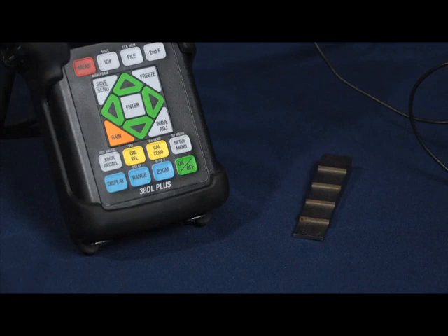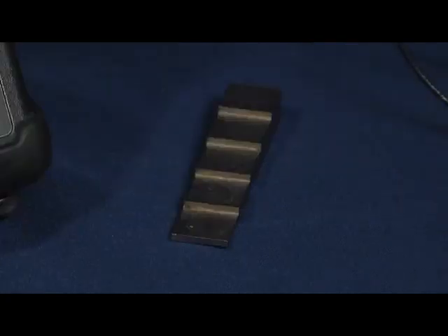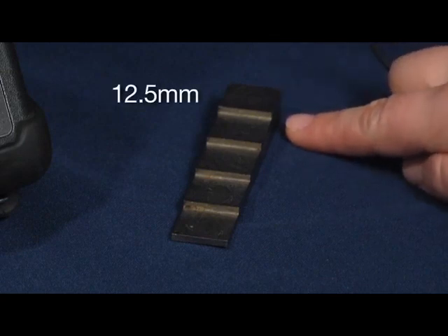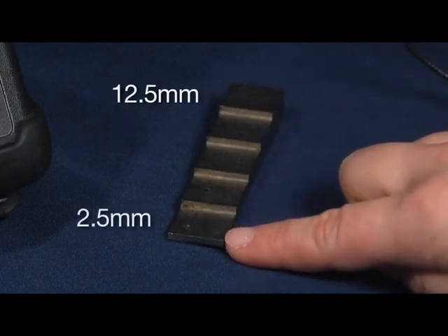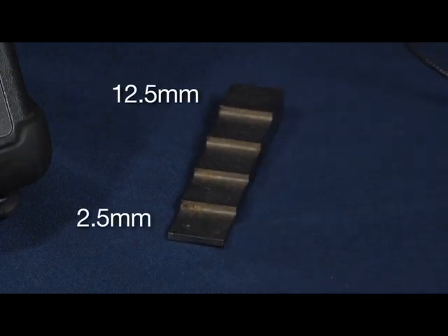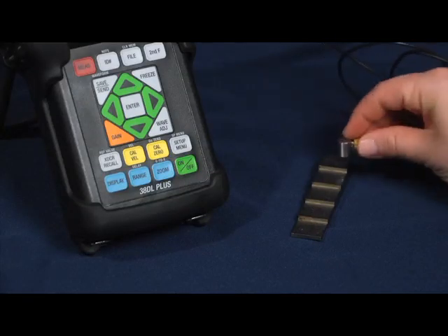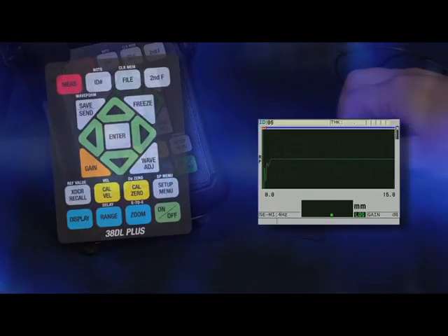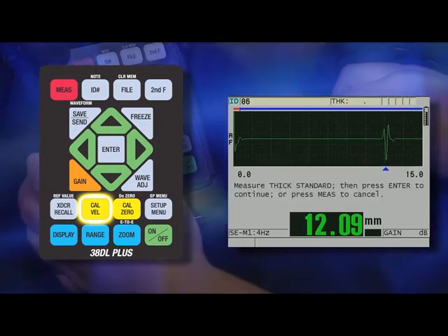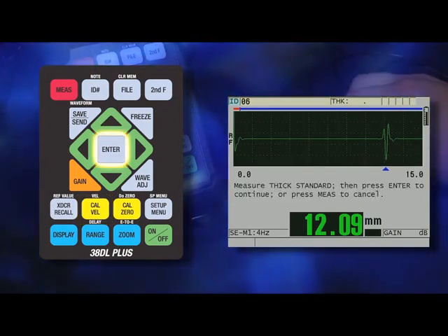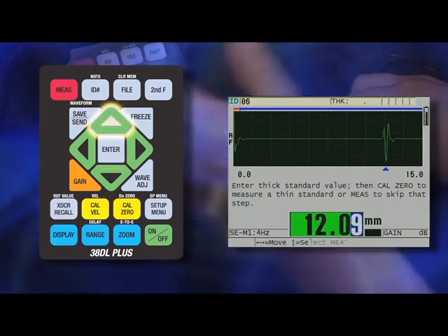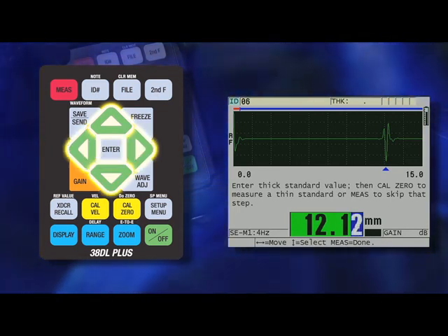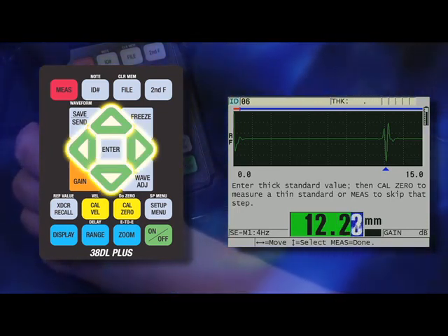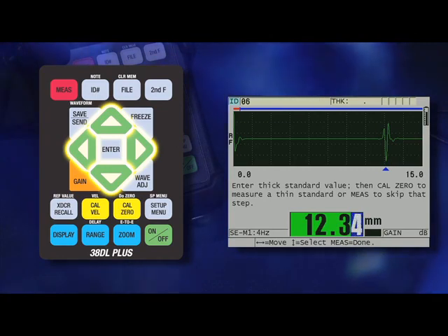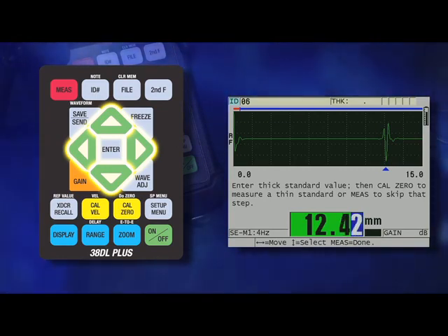At this point, we are now ready to calibrate. We will be calibrating to a 5-step carbon steel test block with a maximum thickness of 12.5 millimeters and a minimum thickness of 2.5 millimeters. Now let's couple to our thick sample and press the cal-vel key. As we get a steady thickness reading, press enter. Now use the up, down, right, and left arrow keys to enter the known thickness of the block. In this example, it is 12.5 millimeters.